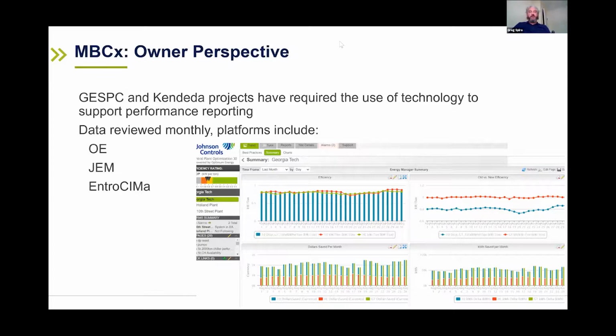This project was about our chill water distribution, going from a primary secondary system to a variable primary system, putting in the Optimum Energy platform to optimize all our equipment. We've gone from over a kW per ton in production to the 0.65 to 0.7 range — a huge demand reduction on campus, savings in excess of $1.5 million a year, and we received a $500,000 check from Georgia Power for that demand reduction.